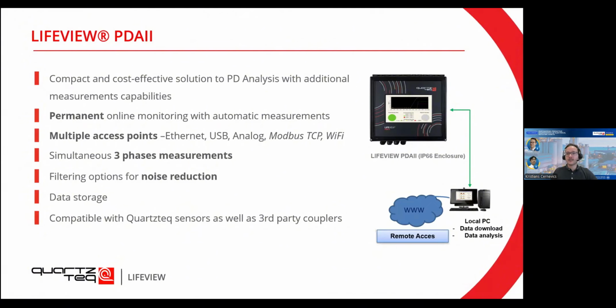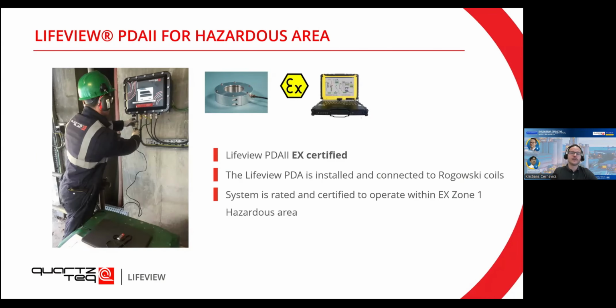And then it's compatible with the Quartzteq sensors we provide, but also many third-party couplers. So if there are already some sensors installed in the machine, it's very likely that you can install a PDA2 and gather the data from these installed sensors. The PDA2 is also adapted for the hazardous area, so it's EX certified. It can be installed with a particular type of sensors called Rogowski coils, which are also EX certified. So it's rated and certified to operate in the EX Zone 1 hazardous area. So it's a very similar tool to the one in the previous slide. However, you can see it's enclosed in an EX box.